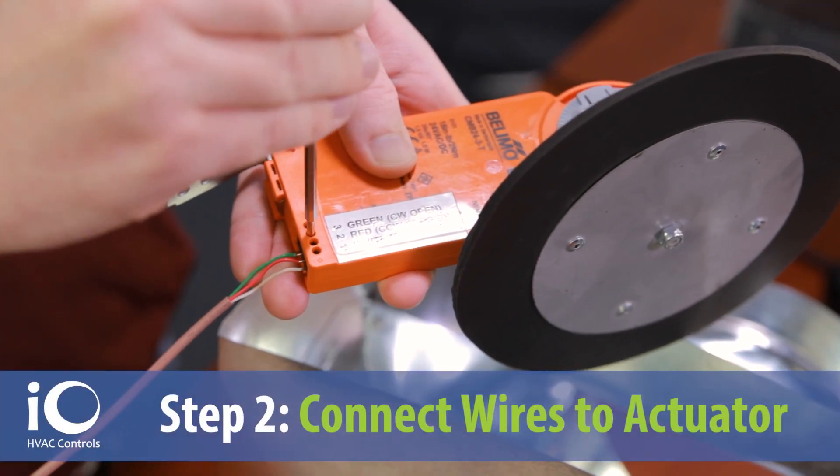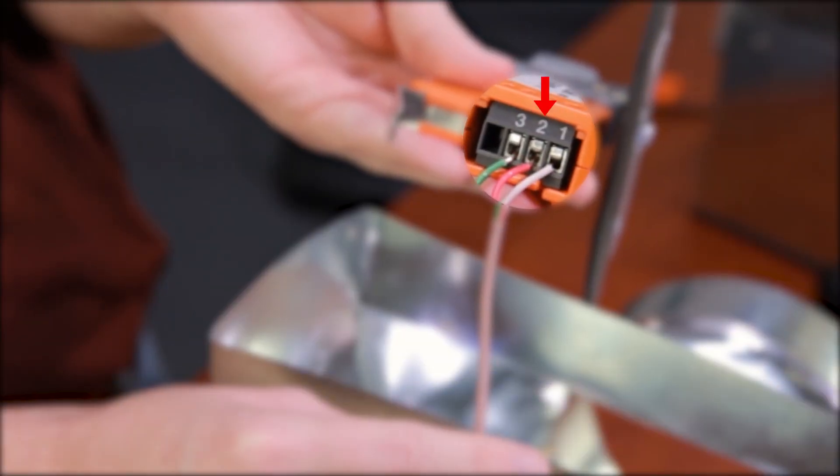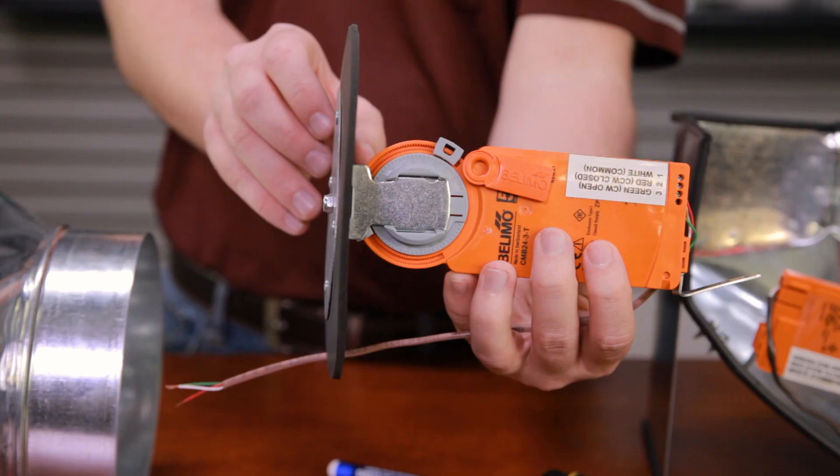Step 2. Connect the thermostat wire to the actuator as follows. One corresponds with common. Two corresponds with power close. Three corresponds with power open.